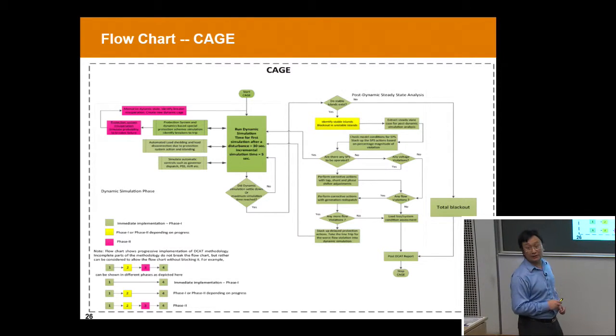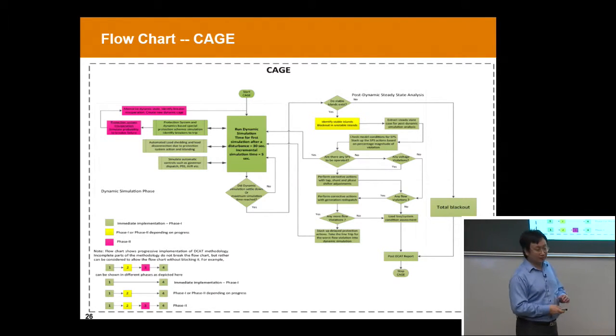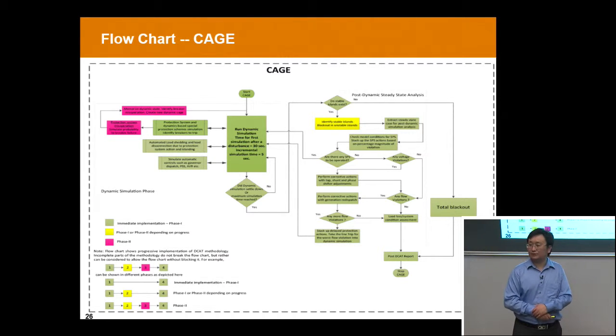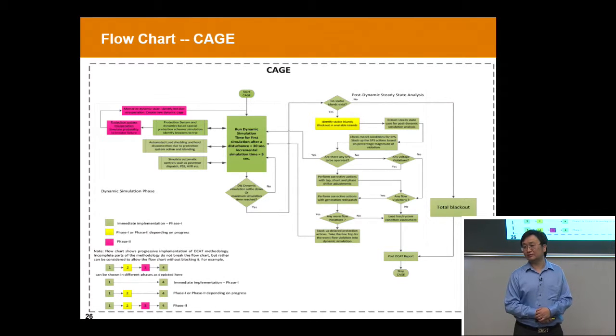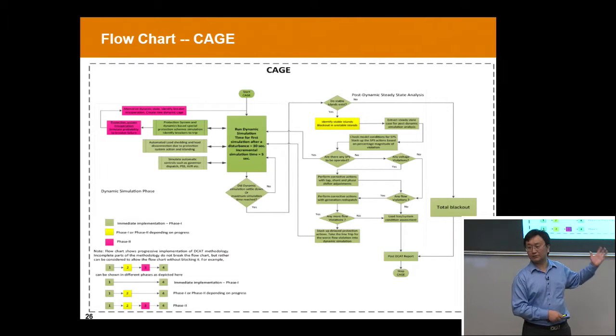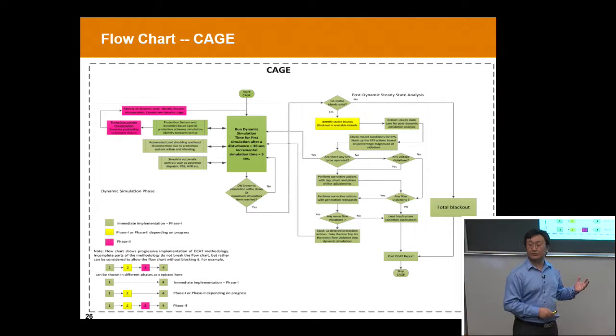We always start with a dynamic simulation, because under severe contingencies—say if you knock out a couple of lines and generators simultaneously—the traditional power flow can easily diverge. Once you have a divergence, it might be caused by a true blackout, or it can be numerical problems causing the divergence. Solving with dynamic simulation will easily resolve the problem.